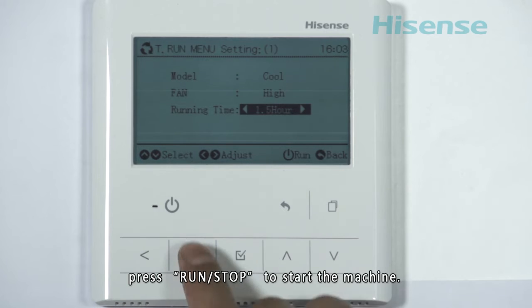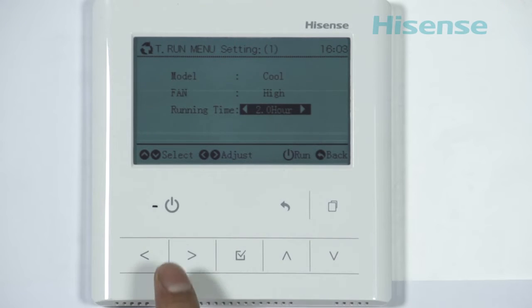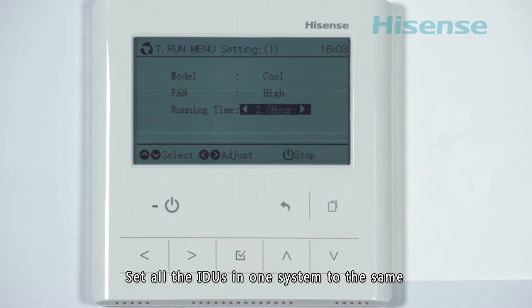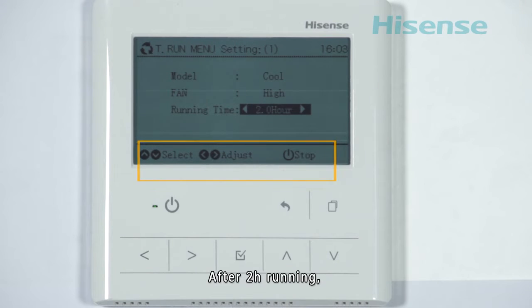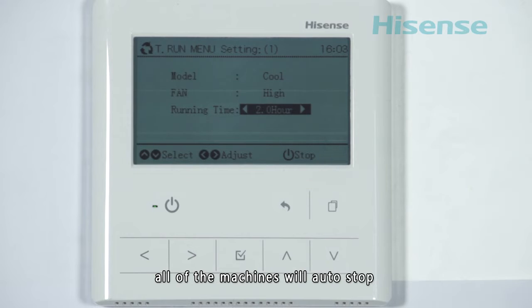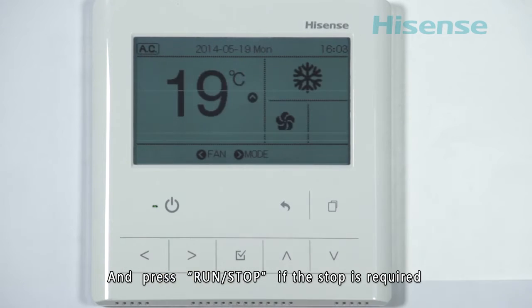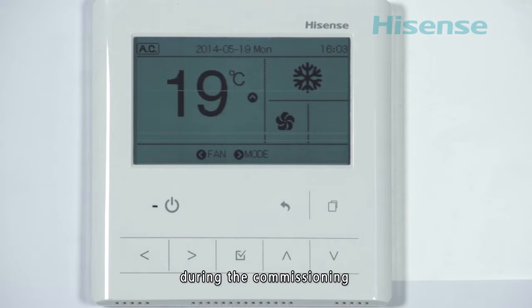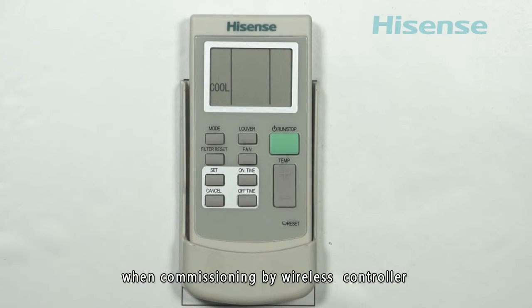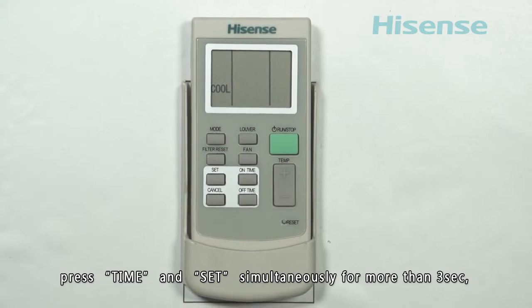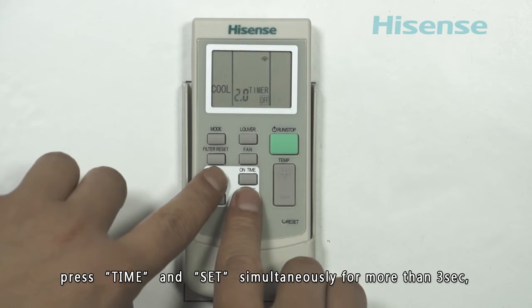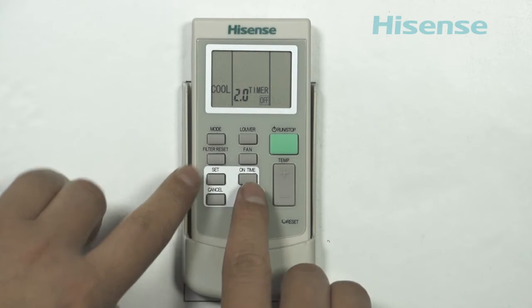Press Run/Stop to start the machine. Set all the indoor units in one system to the same commissioning mode one by one. After 2 hours running, all of the machines will auto-stop, and press Run/Stop if a stop is required during the commissioning. When commissioning by wireless remote control, press the Time and Set buttons simultaneously for more than 3 seconds.